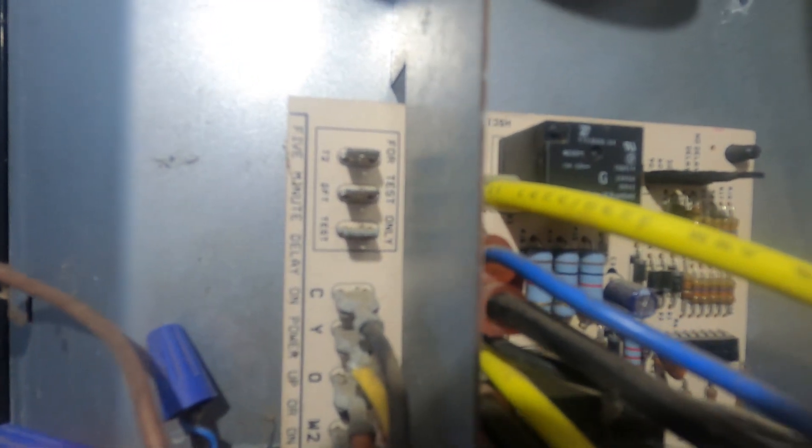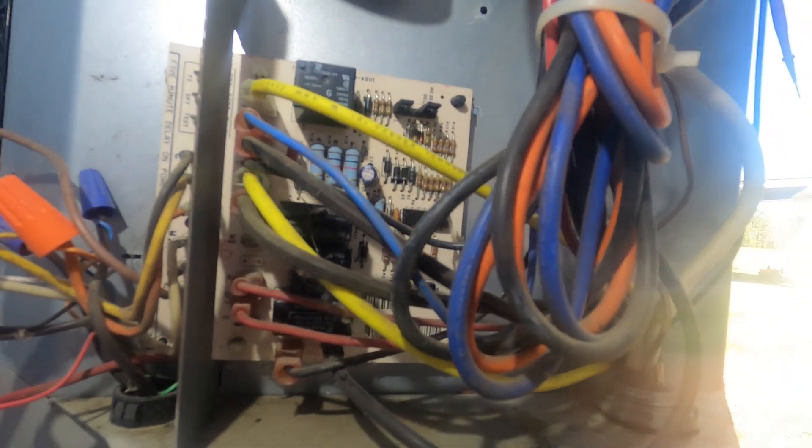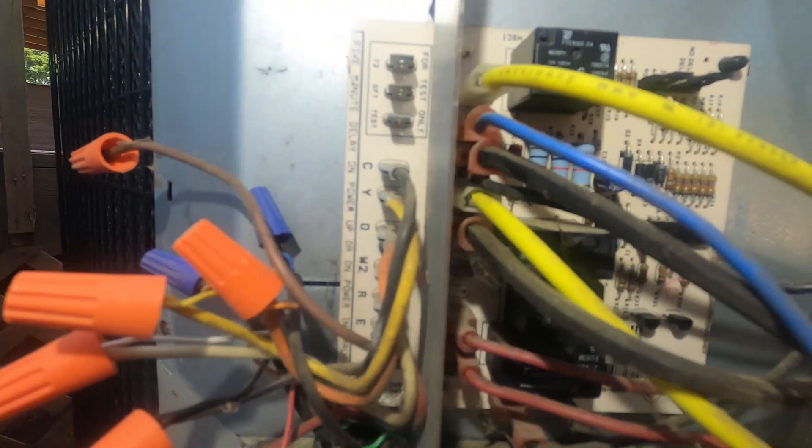This particular brand of equipment is a Nordyne. You actually have to put a jumper between your T2 and your DFT, and then jump common to your test terminal. Once it starts, you'll break the jump to common, and then it'll run in defrost mode until you terminate the defrost by removing that jumper, or it goes into a max timeout — usually anywhere between 10 to 15 minutes on these units — and it'll automatically terminate.